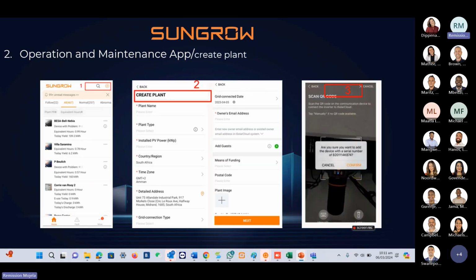And then we have the next part, which is actually just creating a plant. In the app, the moment you finish registering, it will ask you to create a plant. So all these plants that you're going to create are the ones that you're basically going to be commissioning. After you have connected the system to AC and powered up the inverter, you can just create a plant directly on the iSolar Cloud, and this will also run through the commissioning process. So the moment you finish your connection, you power everything on, you go to your iSolar Cloud app, you press create plant, and it will create the plant while at the same time commissioning that particular plant.